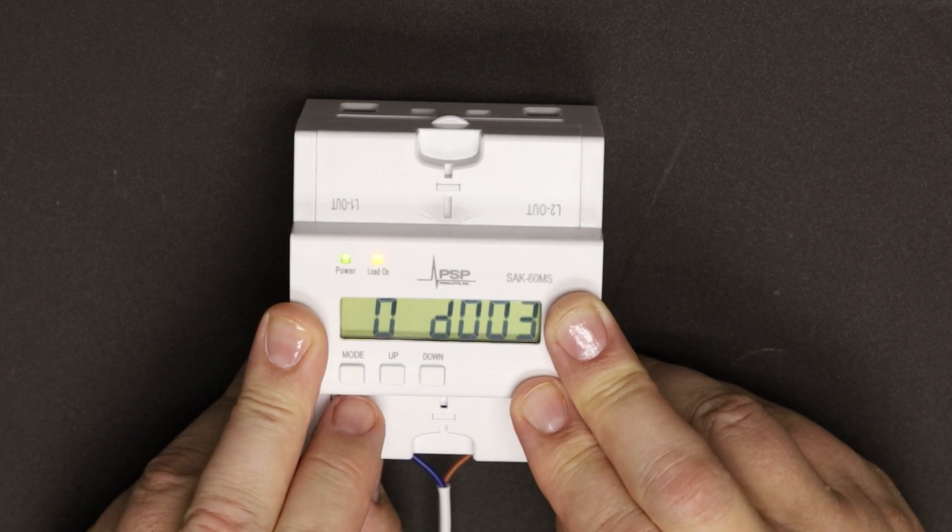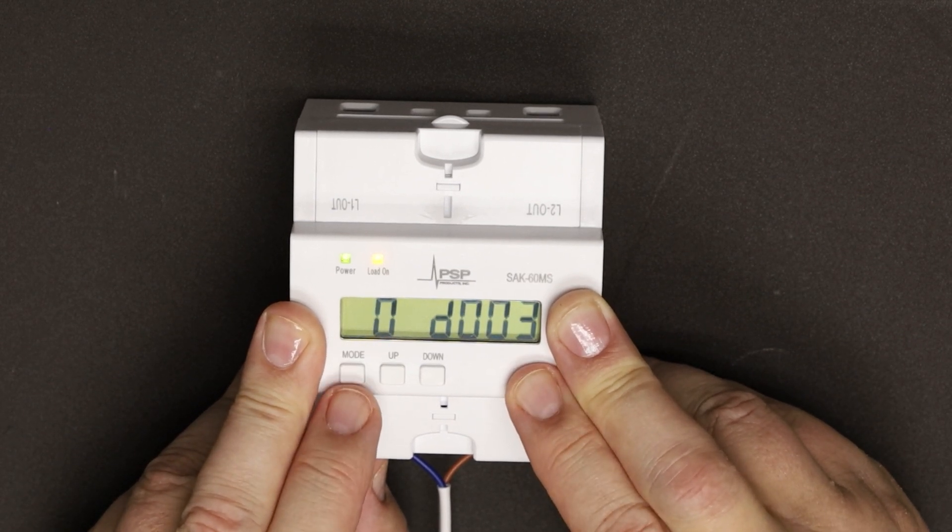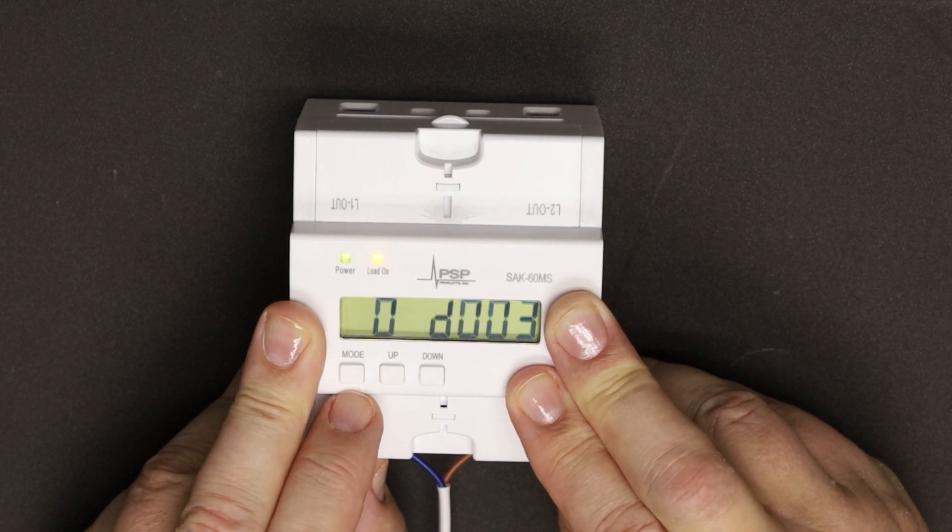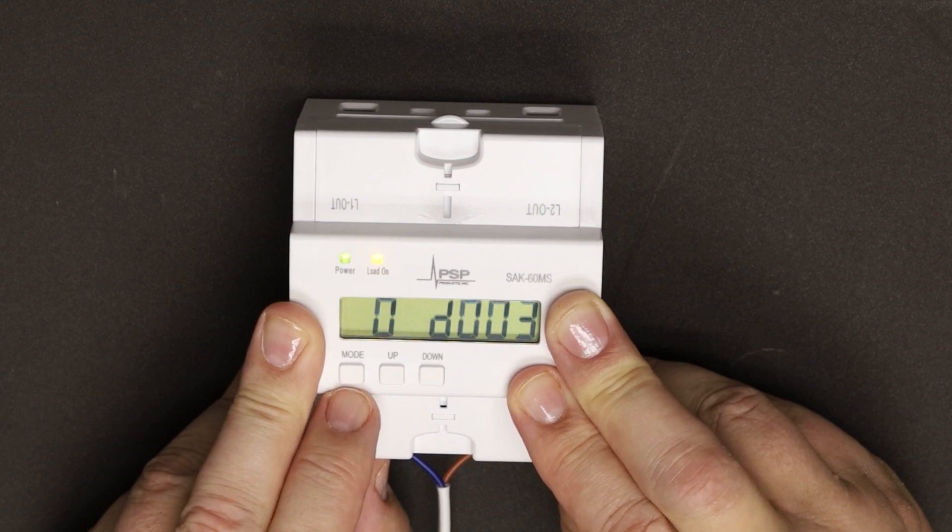OD is the off delay. This is the period of time that the panel will have to be at the high current set point before it sheds the load.